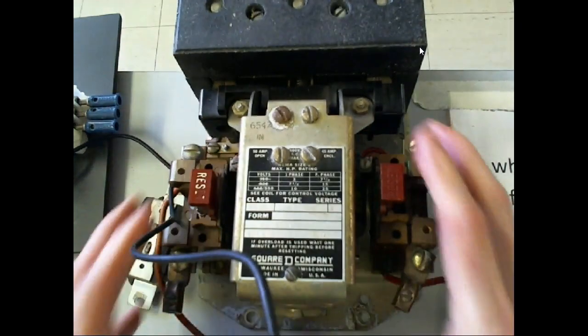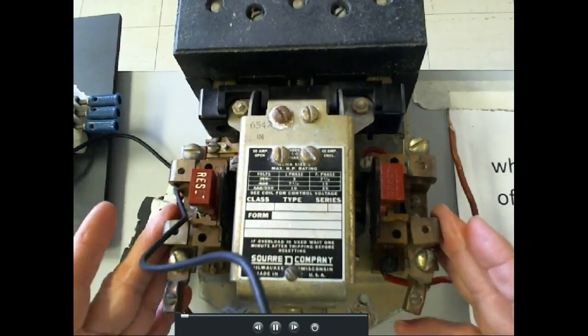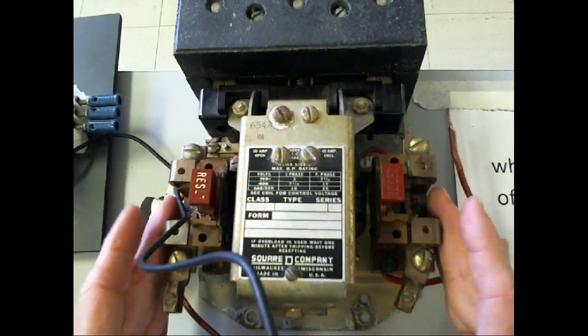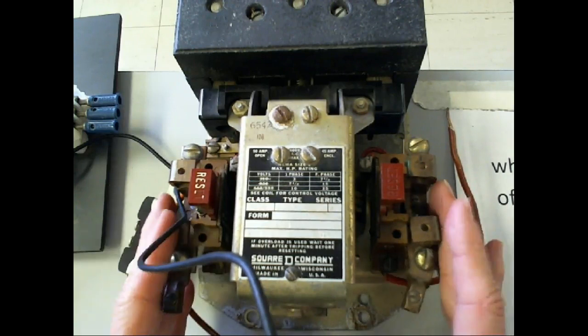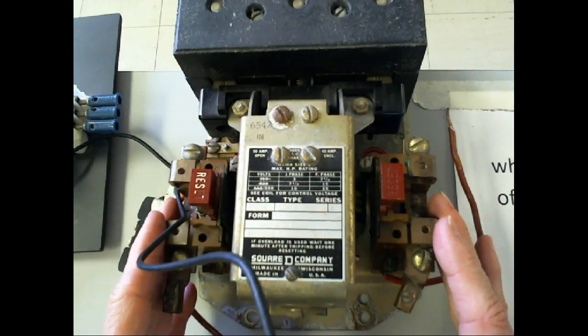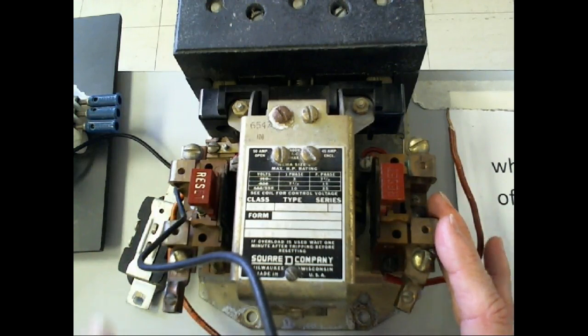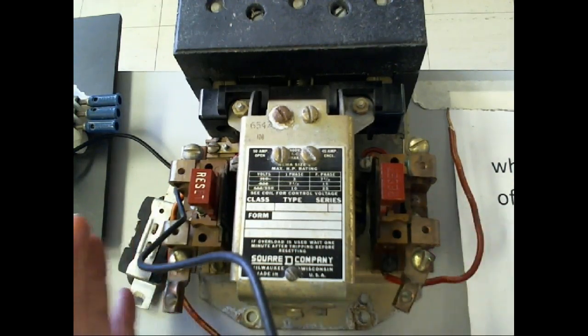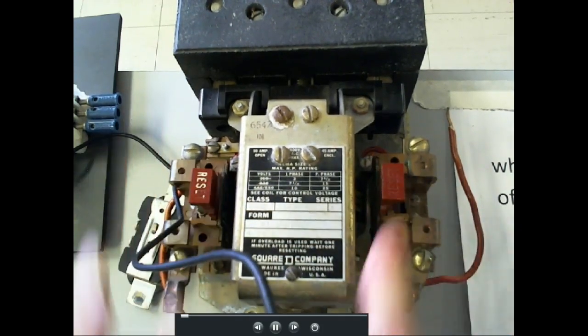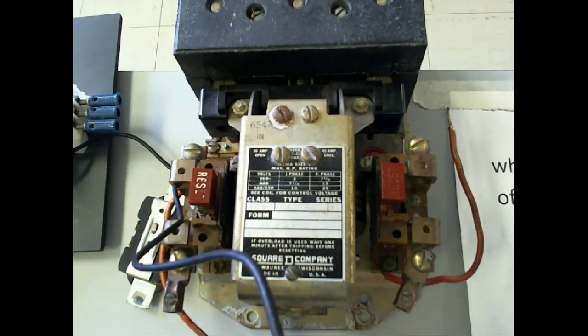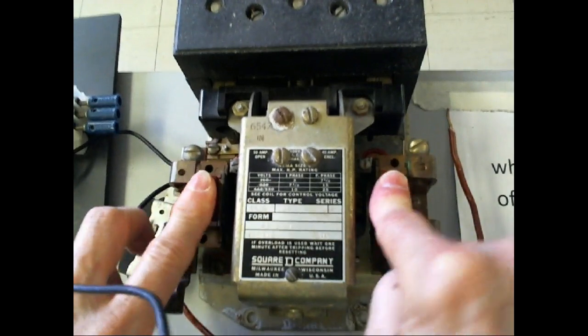And because this is illegal now, what they did on this one, originally they thought that they could protect the motor with just looking at two phases of a three phase circuit. So now we look at all three phases. So now you have overloads in all three. Originally, they had overloads in two. And then they had a reset for at least three phases. And then they finally realized that the center phase can have a problem, and if something happens to the center phase, the other two overloads wouldn't detect it. So that's why you won't see this anymore.